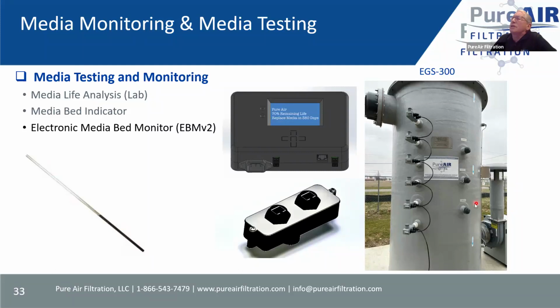It basically goes into the media bed at a 45-degree angle, and it will corrode, whether it be H2S or chlorine. Once the chlorine is absorbed or has expired the media in that area of the vessel, it will corrode this rod, giving you a manual indication. It almost works like a dipstick on a car. You literally pull it out, look at it, and see how much of the media has expired in the container or the vessel.